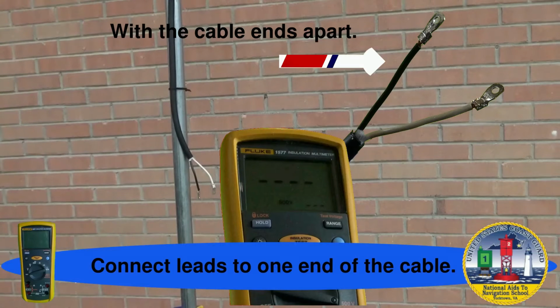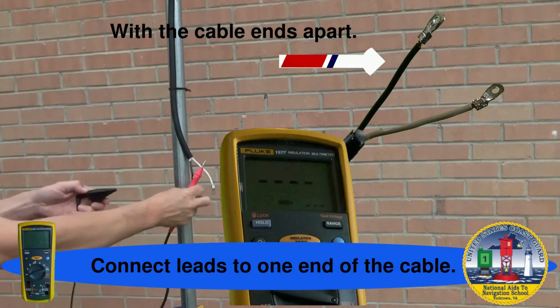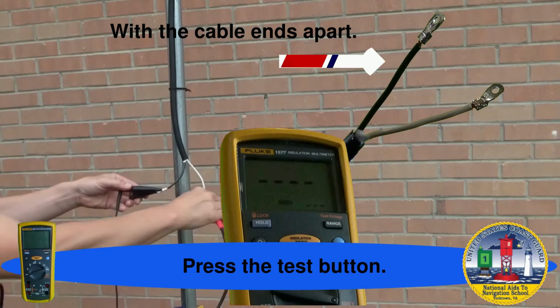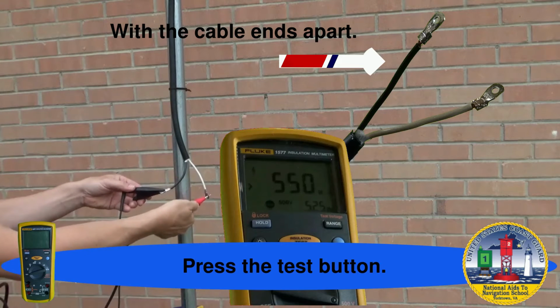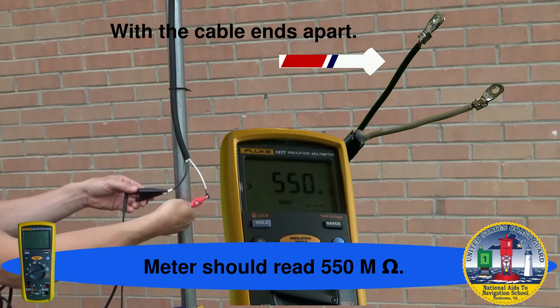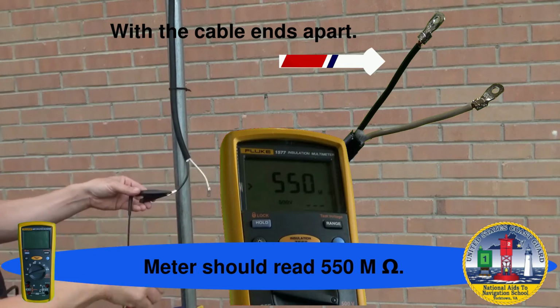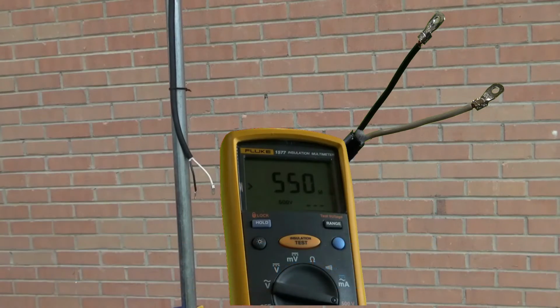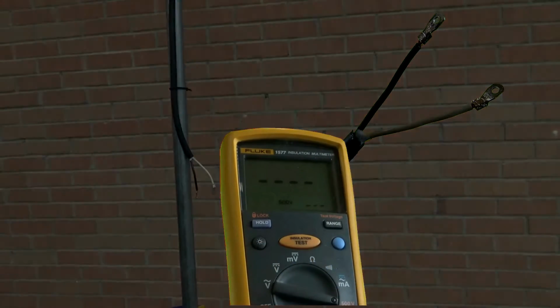With the cable isolated from other equipment, connect your leads to one end of the cable and ensure the other end's leads are apart. Press the test button and the meter should read maximum resistance. Note, in your servicing guide, the reading is only required to be greater than 1 megaohm.